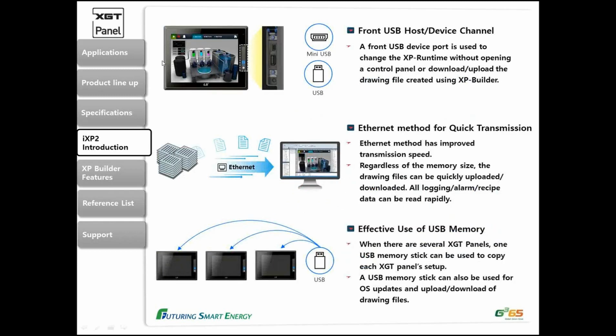We kind of already mentioned this front port, so you can see it better here. There's a full-on USB port and a mini USB on there. With this front USB port, you could change the XP runtime, which is our own operating system on top of this Windows software, without opening up any control panels or going to the back of the HMI. You could also use Ethernet for transferring projects, or doing anything like logging, alarming, or transferring recipe data. That'd probably be best suited for Ethernet since it's overall a faster communication method versus serial.